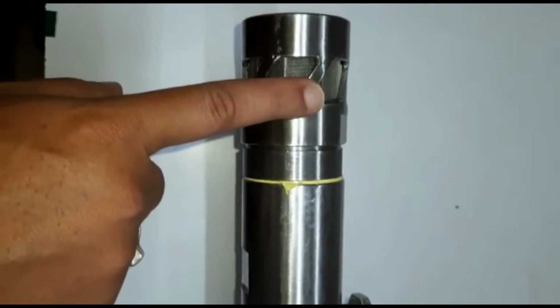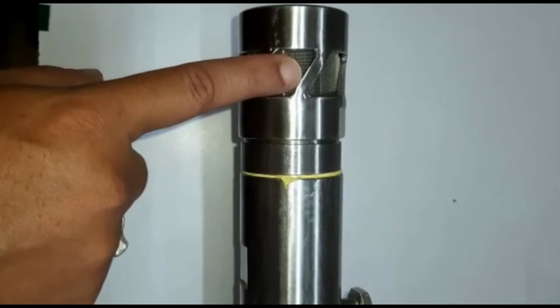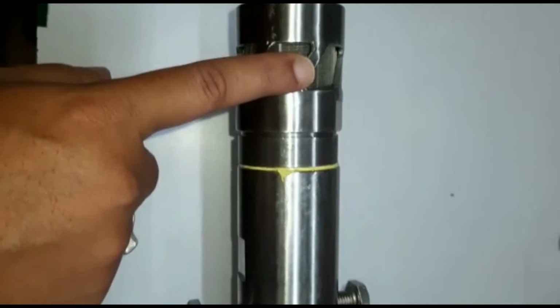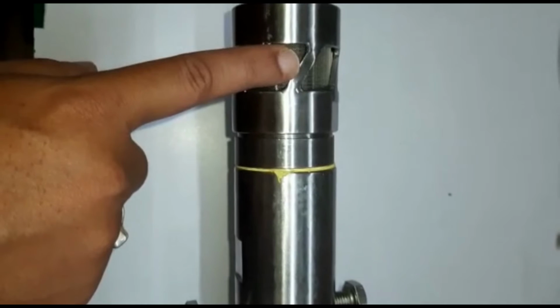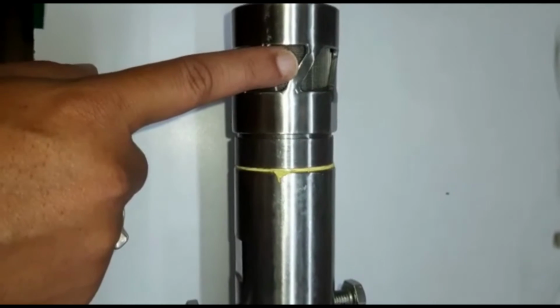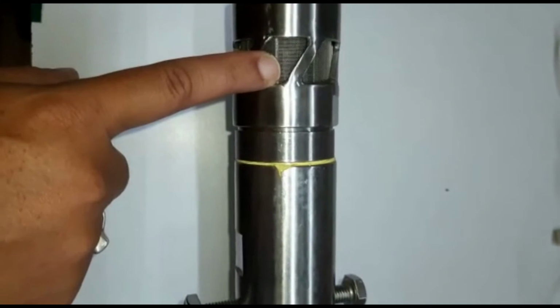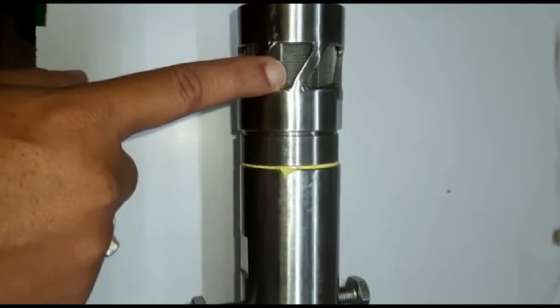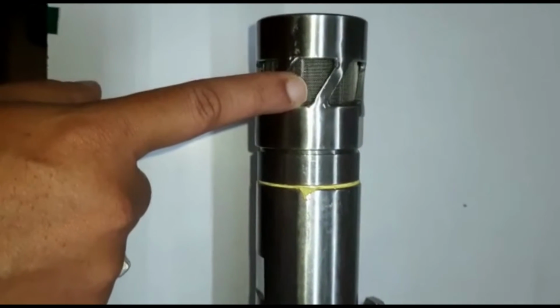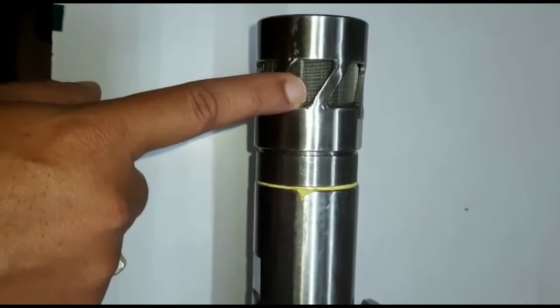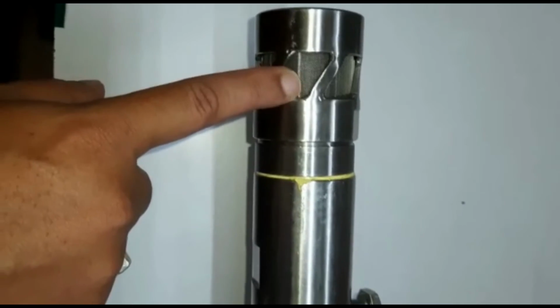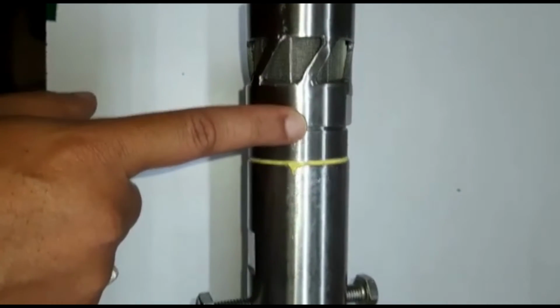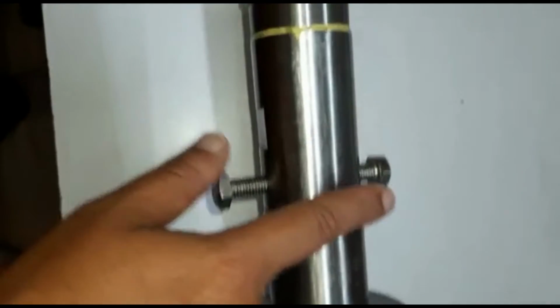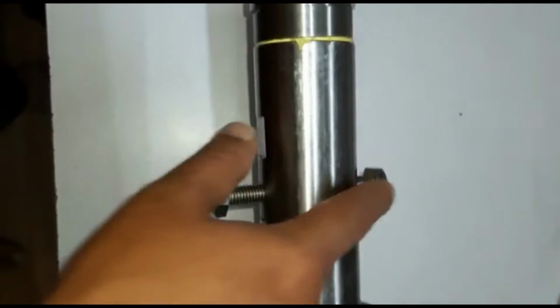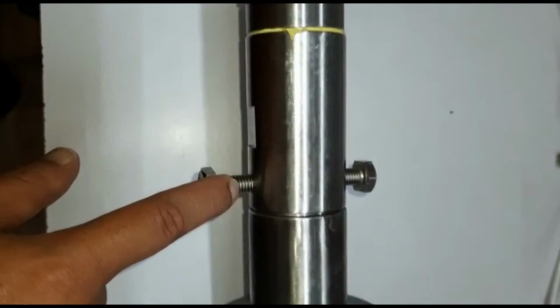But when you put it back, you need to make sure that this is not wet. It is completely dry, so that we don't want water vapor or water droplets to come in contact with the oxygen sensor, because the oxygen sensor does not like thermal shock. It can crack and it can get damaged. So that's one precaution.